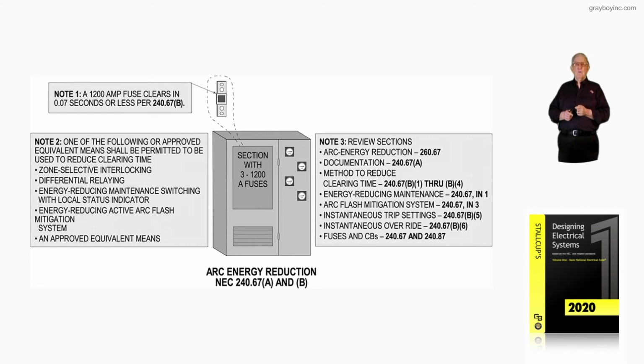Now look at note 3, reviewing sections. If we wanted to know the arc energy reduction capability of this system, 240.67 starts us in motion. But notice documentation is required. We must document just exactly what this system would provide in 240.67A, but we go there to get that information, or again, review our design book, volume 2. Now, the method to reduce. It clears quick. You see up there, 0.07 seconds. That's our clearing time, and it's going to reduce the energy. But because it clears so fast, it doesn't allow the energy to build up as bad.